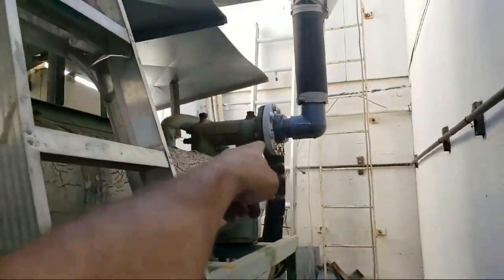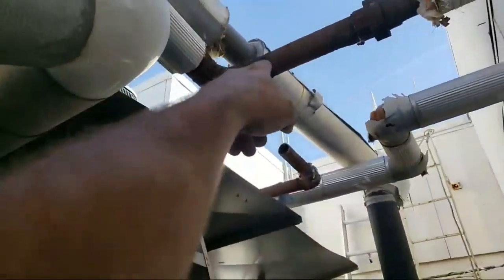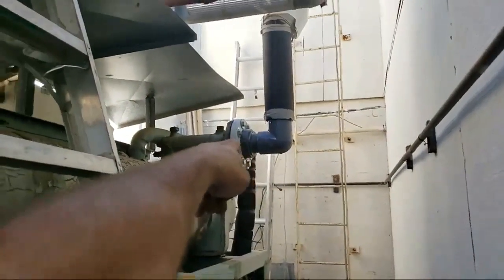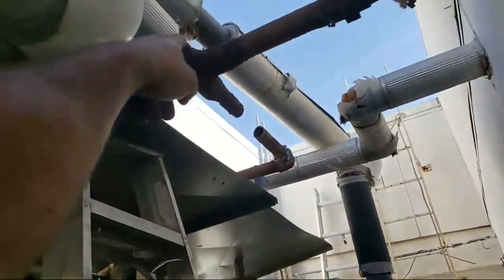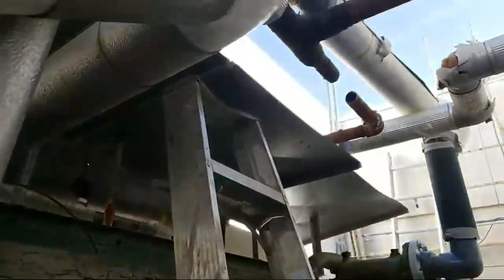This pipe right here, going up and over and back to that connection on the chilled water, that's one of the highest points, and somebody converted it to PVC right there. So he wants me to use a saddle tap, like you do on cooling towers. I guess I could do that.